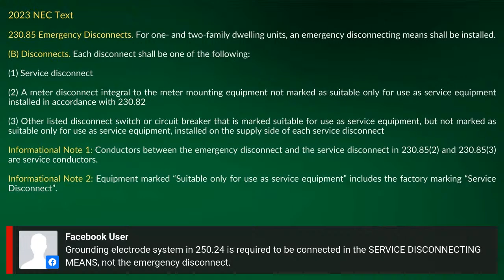I know what he's saying, and what I'm saying is once you establish that first point there, it's telling me that I can have that emergency disconnect marked as suitable for what? For use as service equipment. That's my service equipment at that point. So therefore, 250.24 would apply. But let's just look at it from one other point.